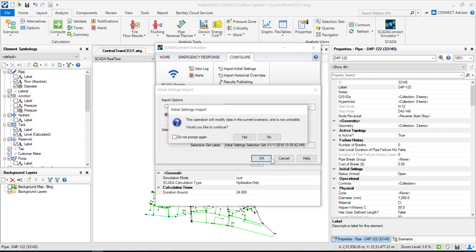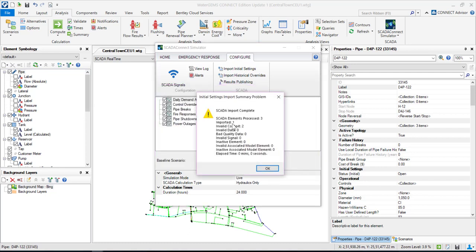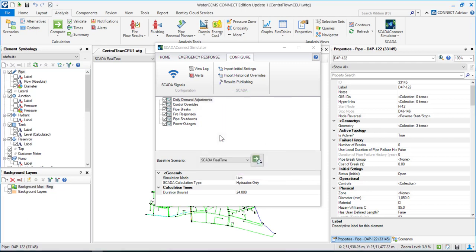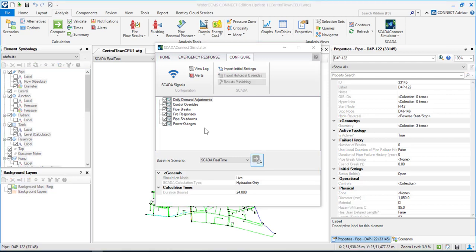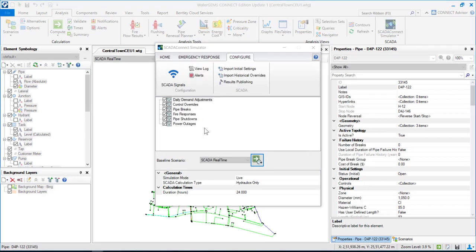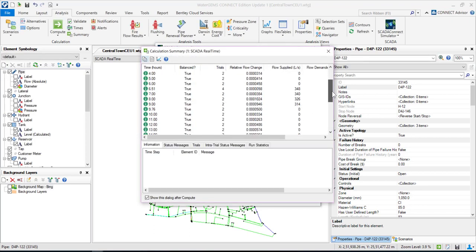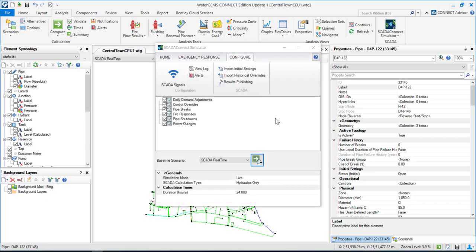If I go to Configure, hit 'Import Initial Settings', and select Real-Time and hit OK — you can see it says 'Imported 1'. It's going to replace the model tank level with the real-time tank level. If I now compute it, the results will be based on the new tank levels — for example, if the tank is full, whether the pump should be on or off.